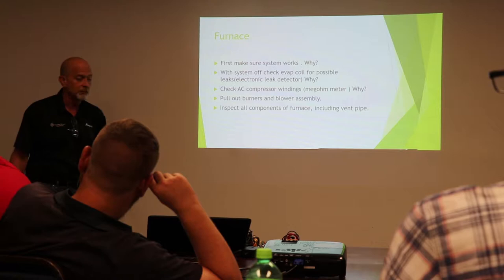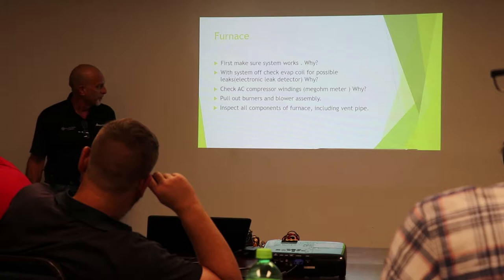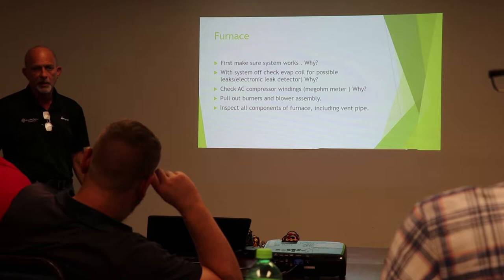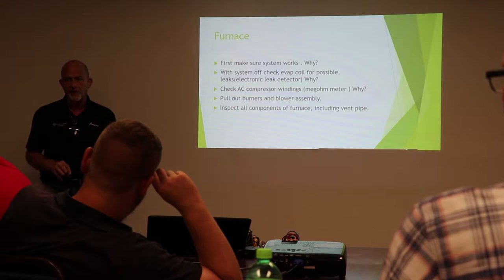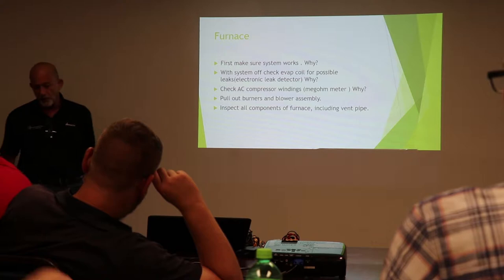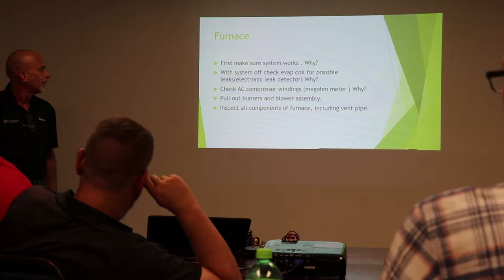All right, already talked about the windings. Now we're going to pull our furnace apart. How many guys pull a complete blower assembly out when they do a cleaning check? Not everybody. There's a reason why, and I'll go over that. Inspect all the components. We're going to go over that, including our venting pipes, what you see, what it means, things like that. We'll pass that around so you guys know about the megohmmeter already.